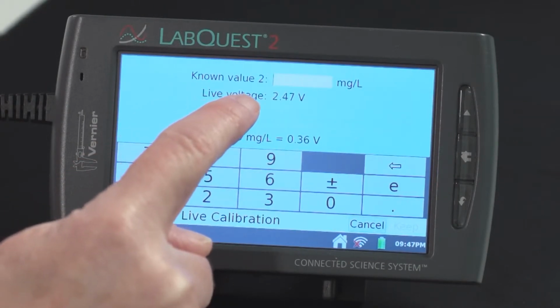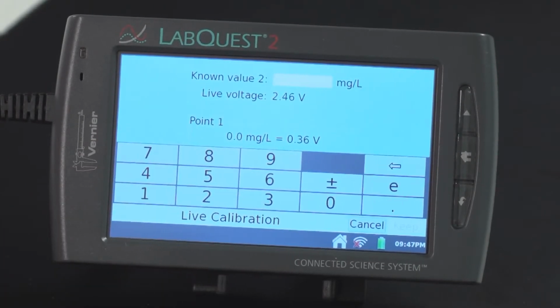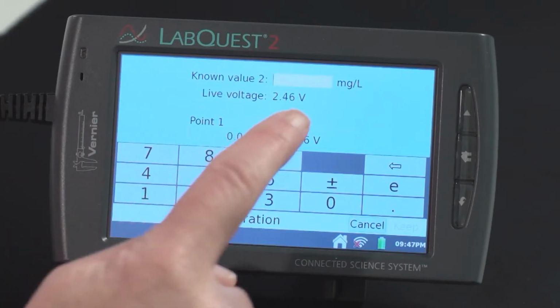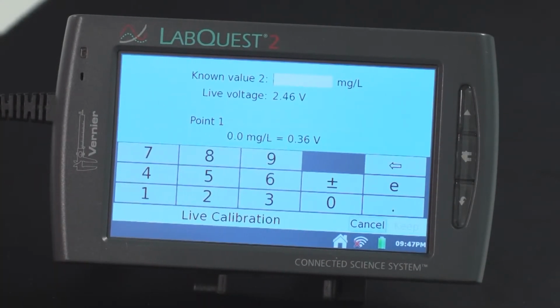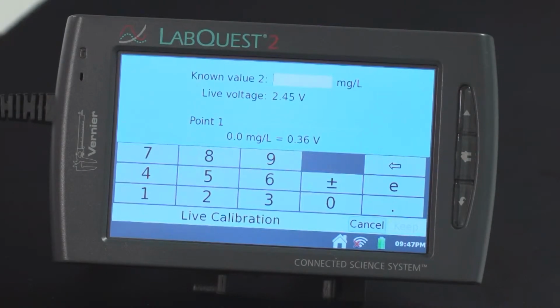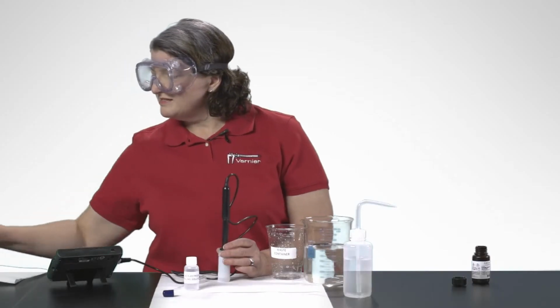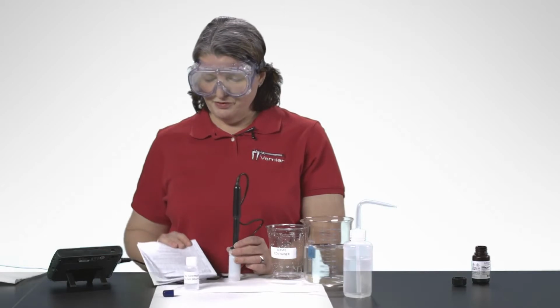It's gone from 0.3 up to 2.4 something. It's still equilibrating there a little bit, but it's close. So we'll let it continue to equilibrate while we look up how many milligrams per liter that should be. It's 100% saturated, but that doesn't tell us the milligrams per liter. We find that in the booklet that comes with the probe.